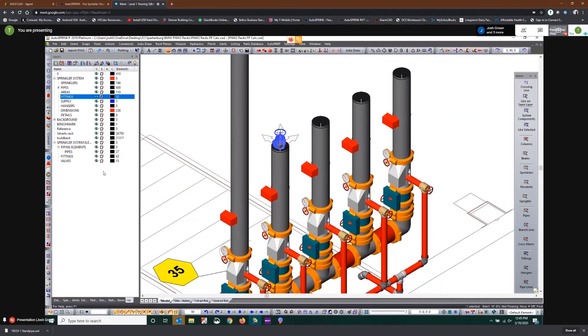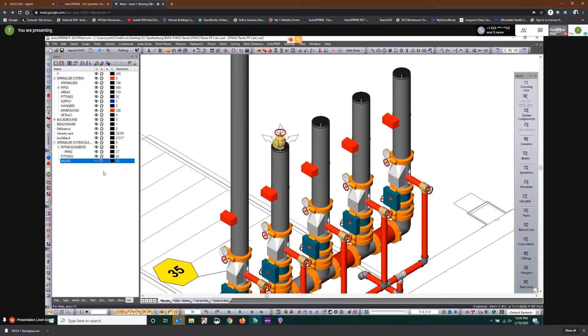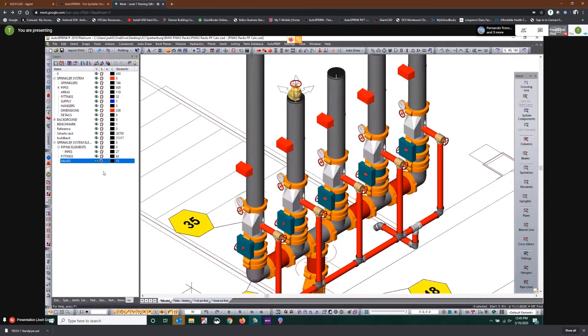So now that we've got that hose valve connected to piping that is connected to supply piping, valve is open, looks good. Just a heads up that when the program calculates this, it's going to include that flow and discharge that hose at that exact flow rate. That flow rate will not change or adjust. That's how the program treats a hose valve when we set the flow state to fixed flow. The program will maintain that flow rate and it will adjust the k-factor of that discharge device based on the pressure at that point.